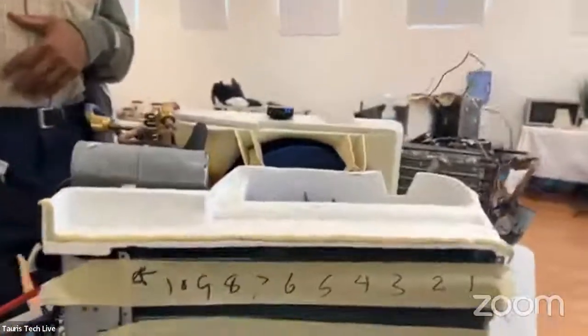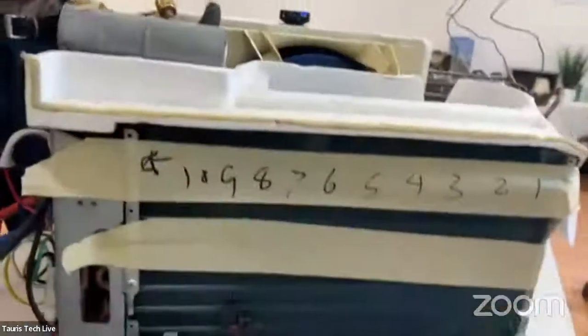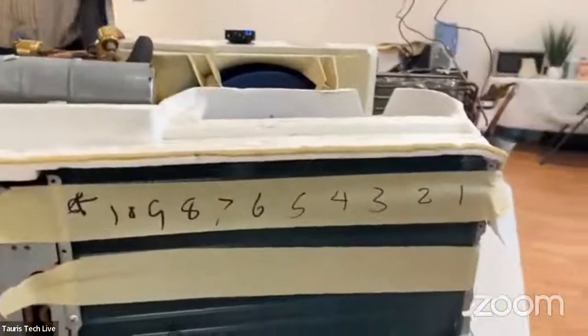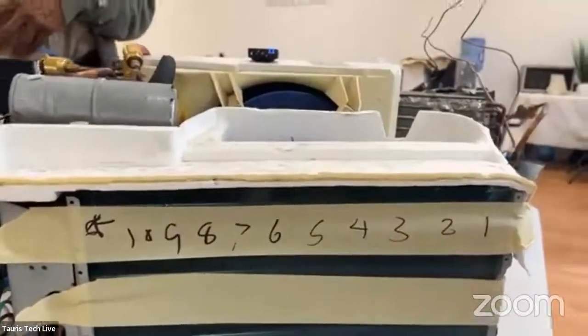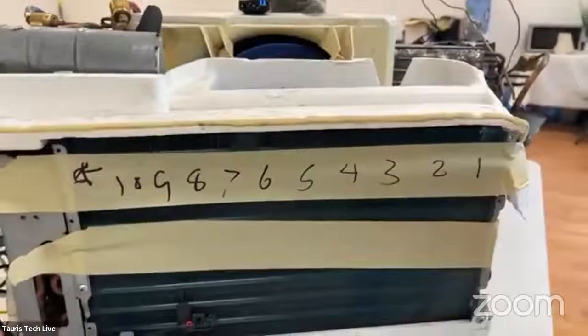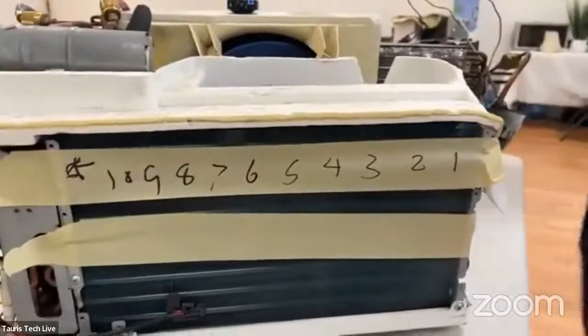But let's say instead we starve the evaporator. So if we starve the evaporator, hang on a second. Sorry. If it's 40 degrees boiling, shouldn't it be 30 degrees? No, because superheat is above the saturation point. It is above the saturation point.